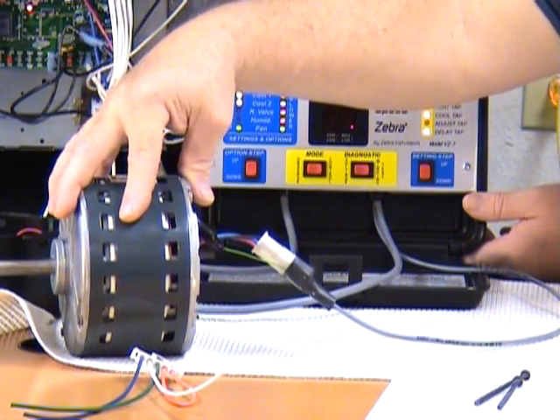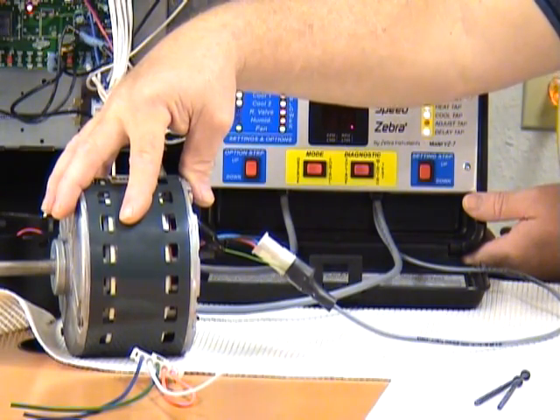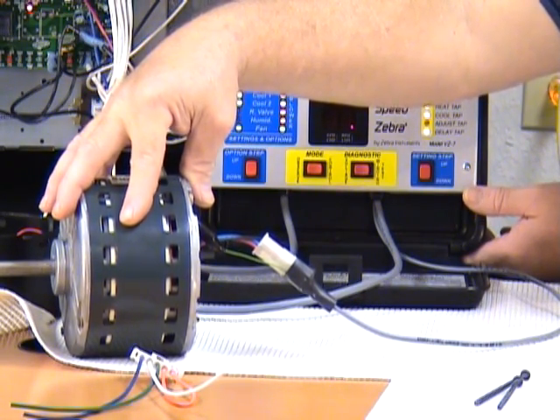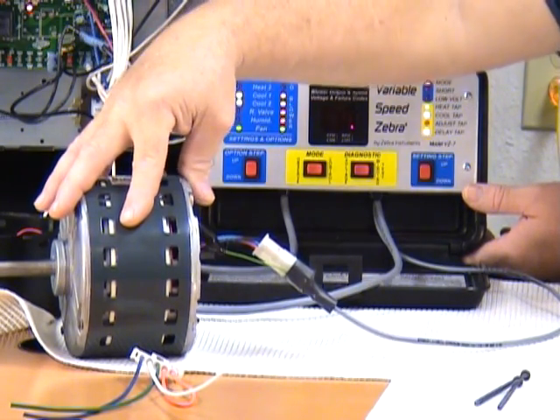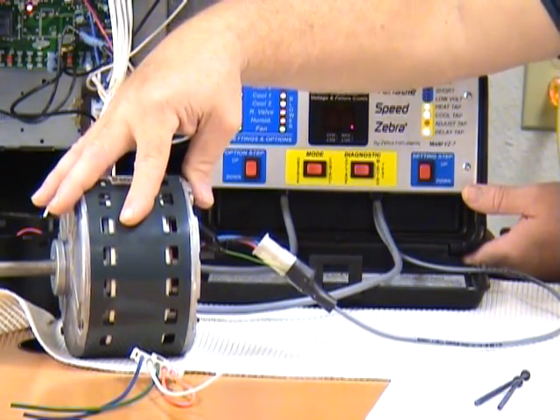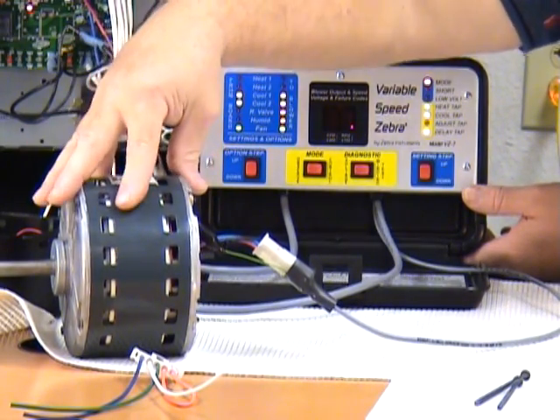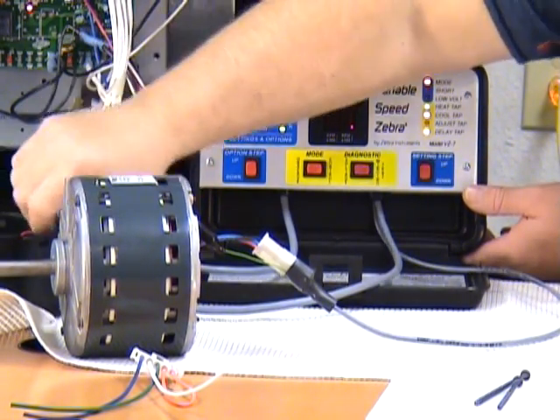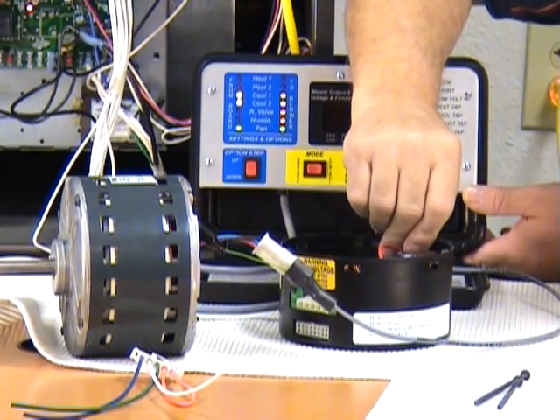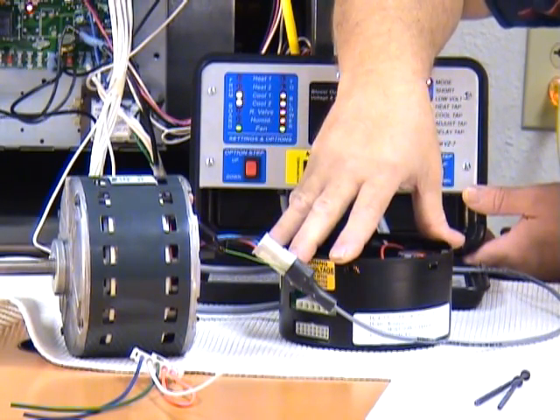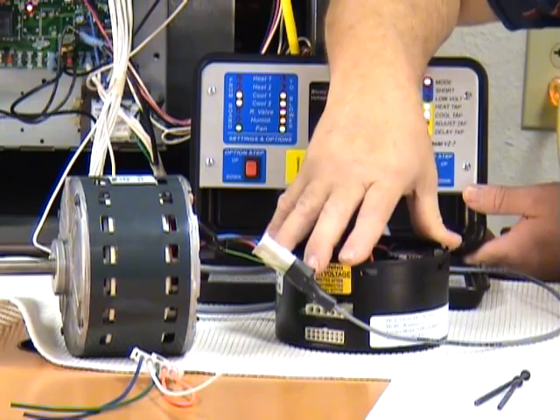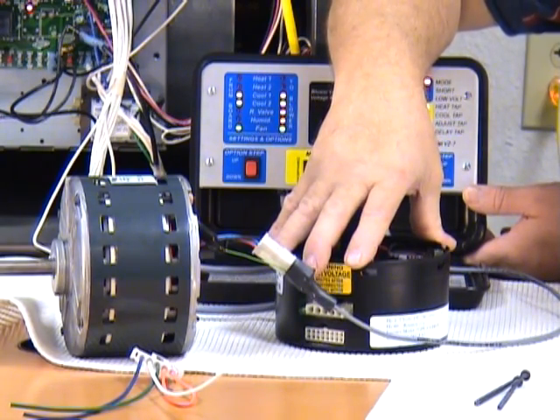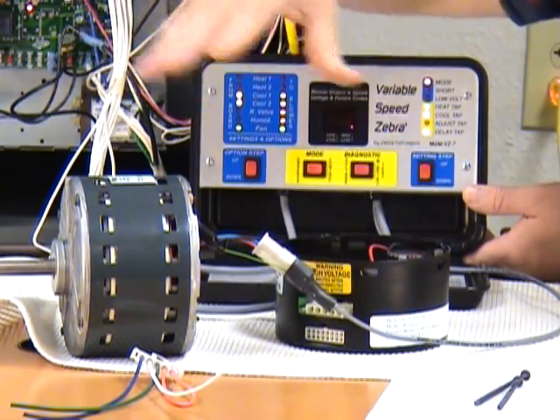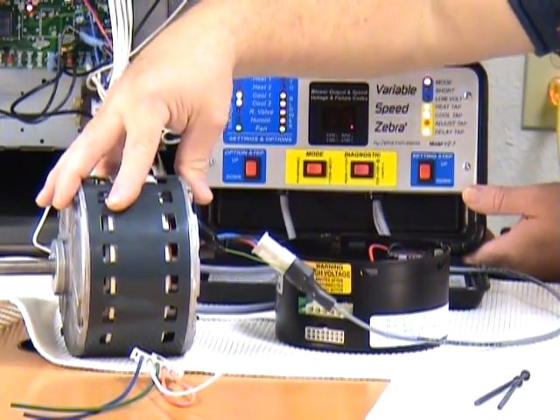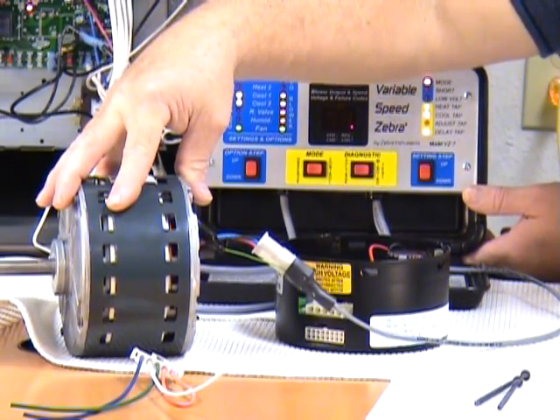Don't replace this unless your motor manufacturer will only allow you to replace the whole motor as one unit. There's a couple of manufacturers we've heard that are doing that, probably because people were making so many bad choices about sending in the wrong parts. This way you can make an accurate test as what's wrong. You know that the only problem now has to be in this electronics module. They typically cost you, the dealer, less than $100. So hopefully you don't have to spend $400 or $500 for your customer, your cost, to buy a whole new motor assembly.